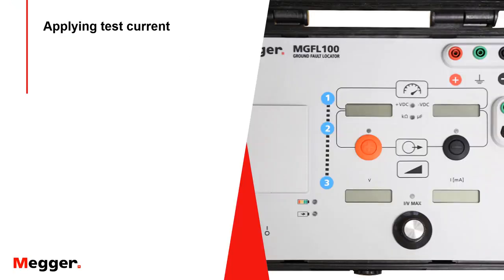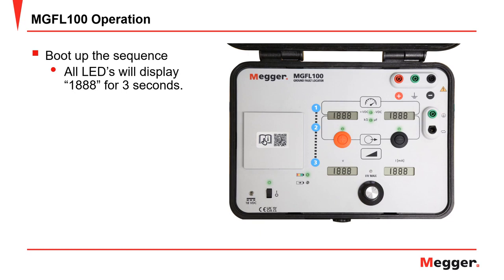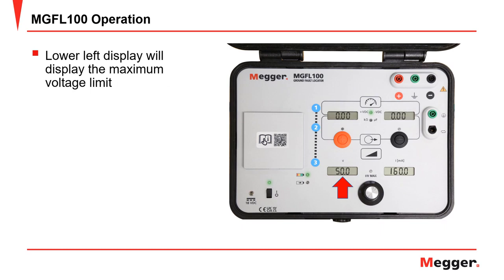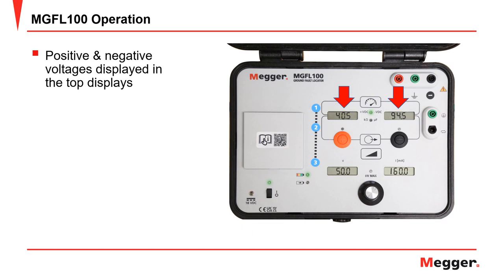Now we are ready to apply test current and evaluate the fault. Turn on the MGFL100 transmitter and allow it to boot up. During boot up, all the LEDs will display 1888 for 3 seconds, allowing you to verify all display segments are operating. The firmware version will then be displayed on the lower left voltage display, and the build number on the lower right. After boot up is complete, the lower left display will show the maximum voltage limit, and the lower right screen will show the maximum current output in milliamps — these values are programmable. The top two displays will show the positive and negative string voltages.